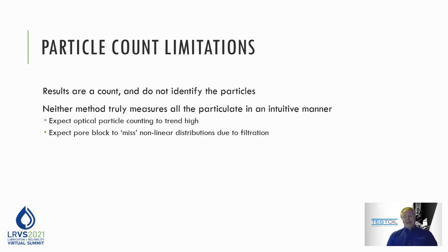And pore block, the takeaway with this one is that it's been generally accepted that because of the way the extrapolation is done, the profile that's expected of flow decay, if you've got a very nonlinear distribution of particles because you've maybe got filtration in the range of one of the micron ratings being reported by particle count, it can miss some of those particles because the flow decay won't match what the computer's expecting. So, warts and all, that's the presentation about both elemental spectroscopy and particle counting.